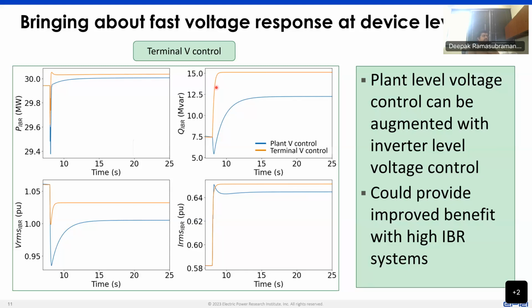The second challenge that might occur is how do these inverters operate when they're close to their limits? So inverter-based resources not only have active power and reactive power limits, they also have current limits. So as the inverter operates closer to its current limits, what kind of behavior will manifest and what kind of properties and services can it continue to provide at those current limits is something that we don't fully know yet.